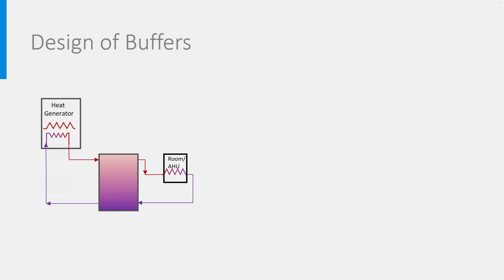Instead of water, phase change materials or thermochemical materials can be used as well, with the advantage of their high latent heat. In this 4-pipe configuration, all heat produced by the generator goes first to the tank. The tank is then tapped to the room emitter or the air handling unit. In the same way, the colder water returning from the emitter goes through the tank, and a pipe at the other side brings it back to the generator.